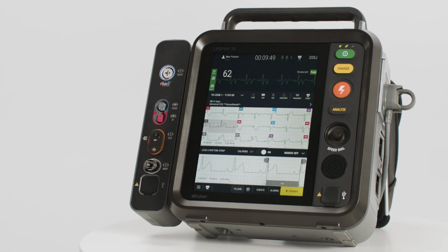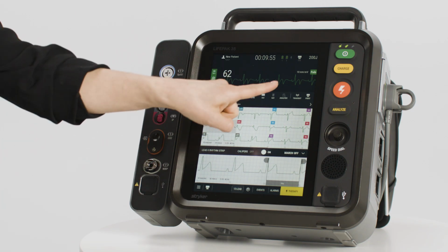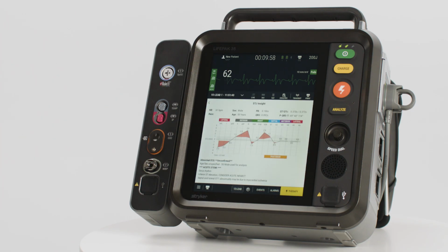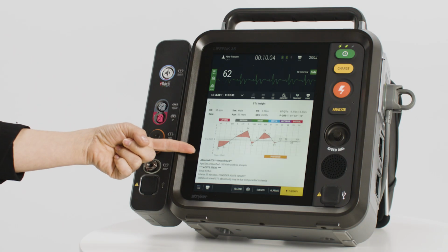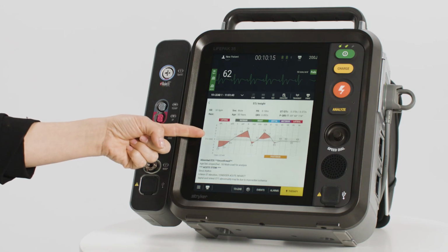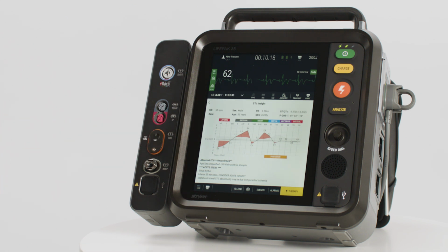The analysis also includes the STJ Insight graph. To access the STJ Insight graph, press the Analysis button at the top of the 12-lead window. This provides a graphical representation of the patient's STJ measurements in comparison to the normal range of ST segments based on the patient's sex and age. The gray band across the middle of the graph represents the normal STJ levels based on the patient's sex and age. The ECG leads are arranged in anatomical order along the x-axis of the graph: limb leads first, followed by V leads. The STJ levels are shown on the y-axis in increments of 1 millimeter.